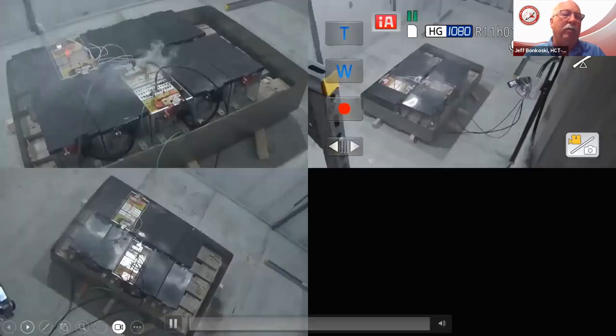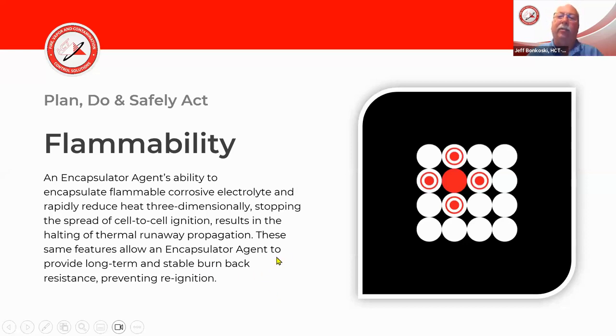We see the temperatures continue to rise. The system activates, and within just seconds, the flames are gone - the fire is extinguished. The system continues to run though, because we want to make certain we're getting enough agent in to encapsulate those electrolytes, so we don't have to worry about reignition. We want to make sure we're cooling those batteries down below reignition temperature and stopping the thermal runaway that's taking place. The system continued to run even after visible flames were gone, to get those cells below the temperature where thermal runaway is stopped.